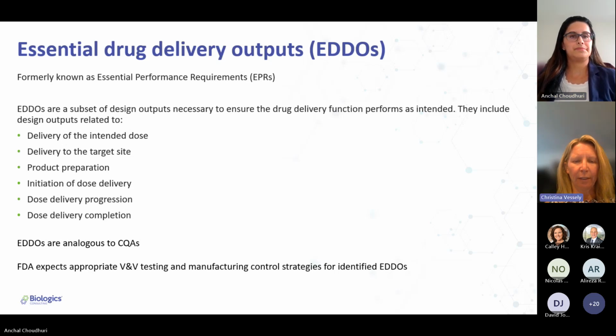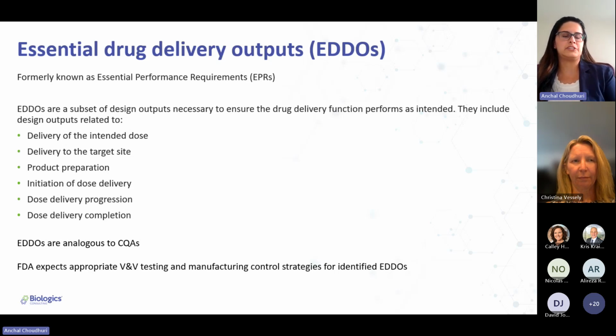And I wanted to jump in again. I know that you're talking primarily about novel devices, but does this new guidance apply also to those off-the-shelf components like the prefilled syringes and things that are already marketed? Actually, yeah, it does. So these EDDOs should be considered for any device, even if you're using something that's on the market. As part of that design control process, you need to look at what these essential drug delivery outputs are, and if they haven't been appropriately verified and validated by the CMO, then that needs to be done, and it definitely needs to be done in combination with the specific drug product or the biologic that's going to be used.